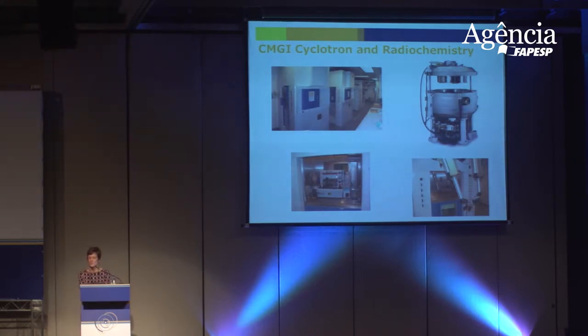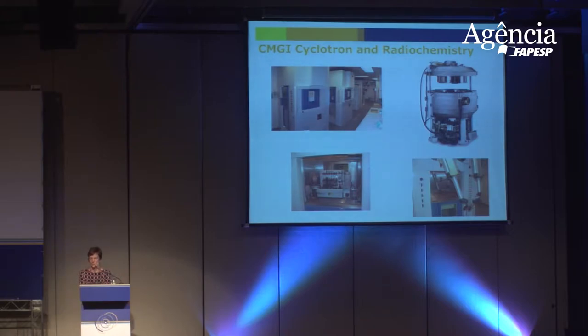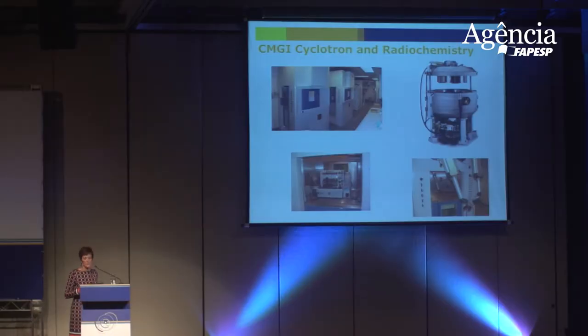To highlight my specialty in radiochemistry — inside our radiochemistry facility we have our 11-MeV cyclotron. This cyclotron is capable of producing the main PET isotopes: fluorine-18, carbon-11, nitrogen-13, oxygen-15, and we've developed solid targetry to radiolabel with copper-64, giving us a longer half-life of 12 hours. Since everything is radioactive, we can't do chemistry with our hands — we use lead-shielded fume hoods called hot cells, and we use robotic manipulators and automated devices.